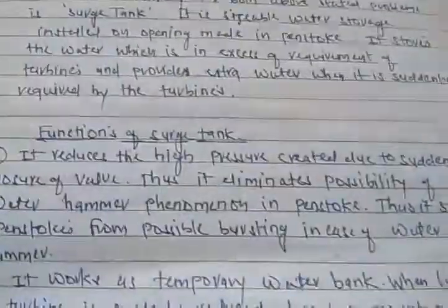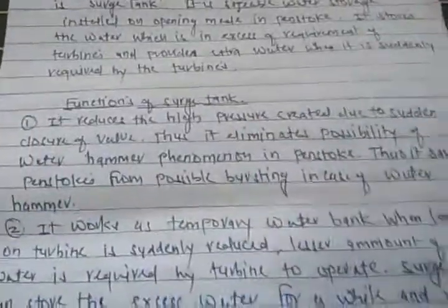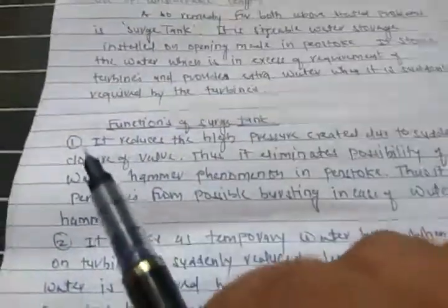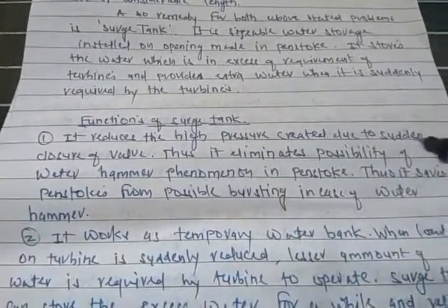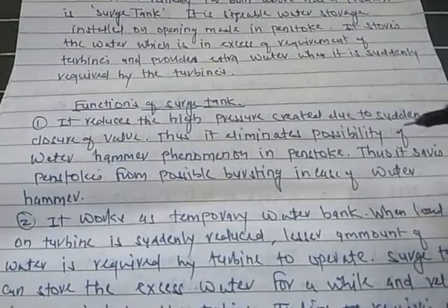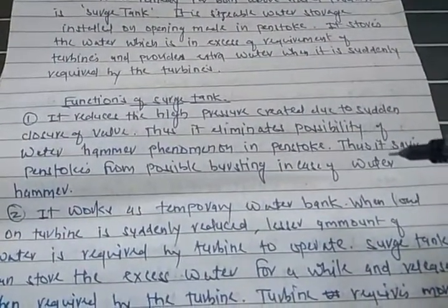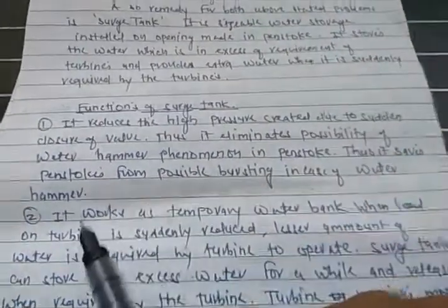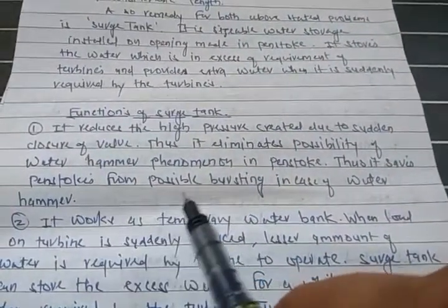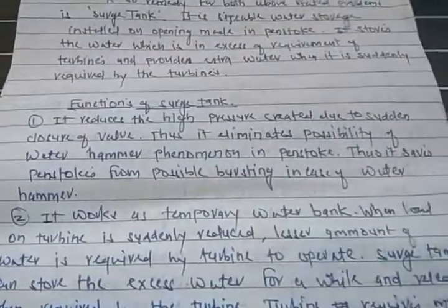Next, functions of a surge tank. This needs to be seen in detail. Many times a question is asked on this. First, it reduces the high pressure created due to sudden closure of a valve. Thus it eliminates the possibility of water hammer phenomena in the penstock, and thus it saves the penstock from possible bursting in case of water hammer.